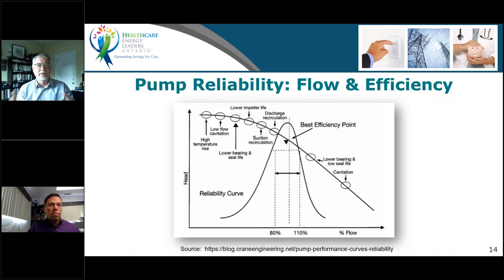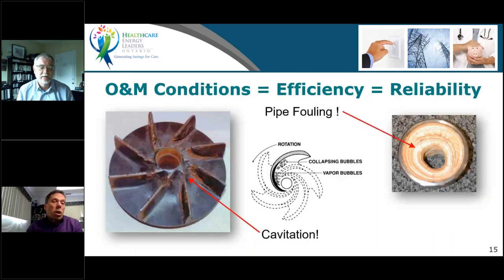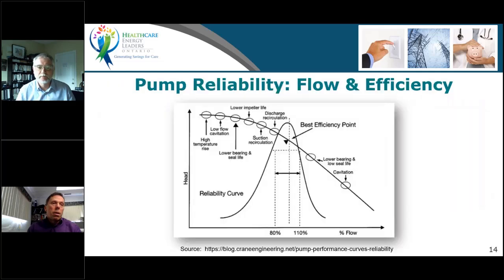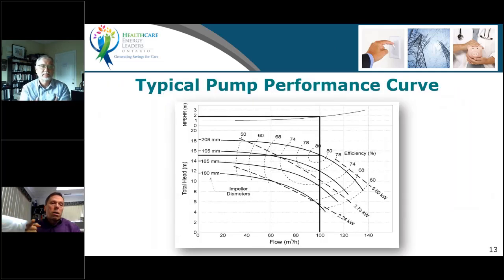Like Paul said, look at it from a maintenance perspective. Look for the pumps that you have to do more maintenance on, and maybe they're going to be the ones that give you more efficiency if you treat them better in the long run. And by the way, this is not hard to obtain. All you need to measure is the delta P across your pump. If you know the model of your pump and you measure the delta P, you can figure out where you are on the curve. It's a very, very easy measurement to take, as long as you can find a pump curve.